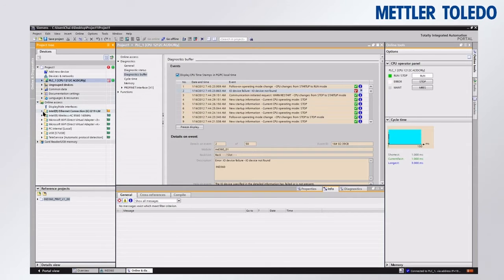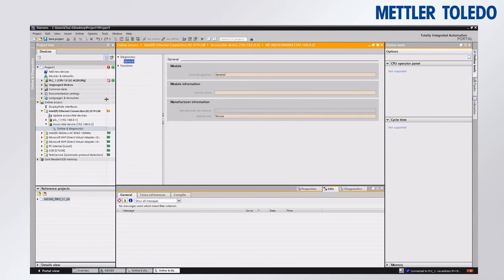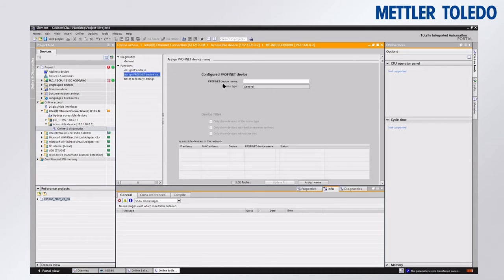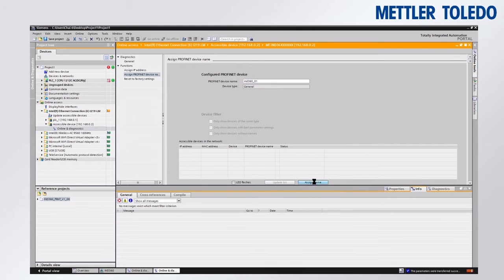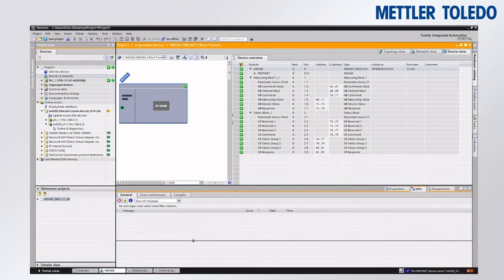We'll go ahead and find the IND360 on our network and assign the IP address and the PROFINET device name. The IP address is the default used by the IND360, but we'll assign it anyway just to be sure. The device name is IND360 underscore zero one. Make sure to hit the assign name button at the bottom. As soon as we do that, we get green check marks all the way down and we are communicating between the devices.